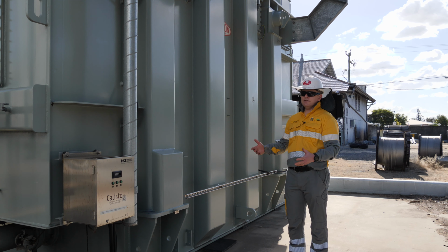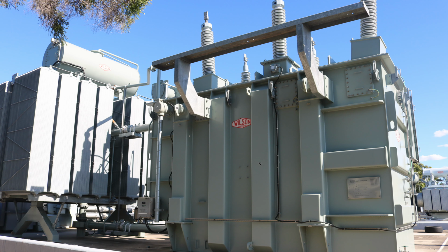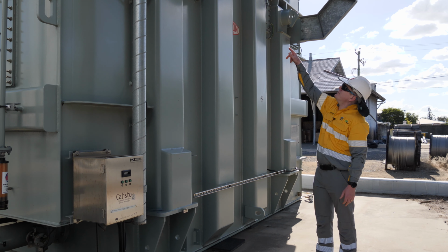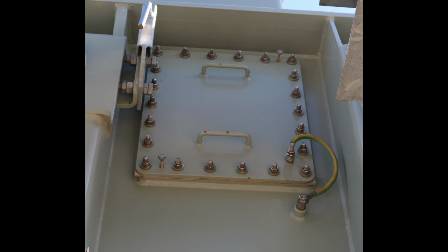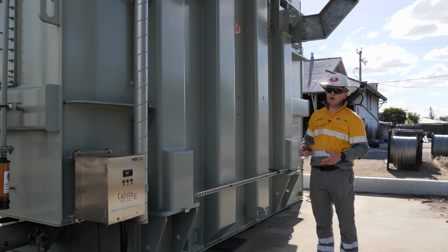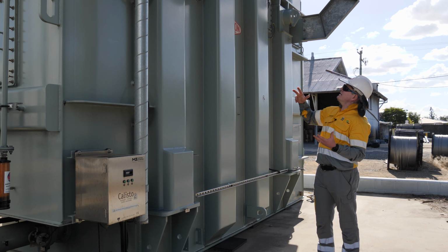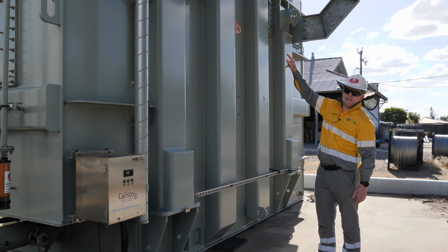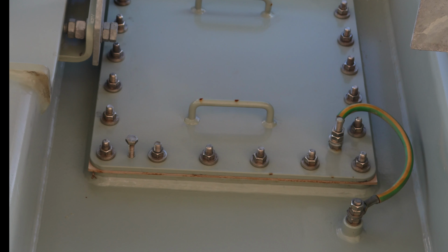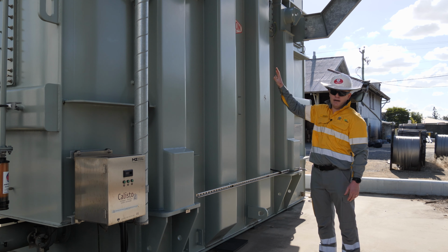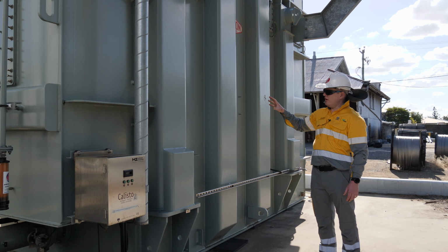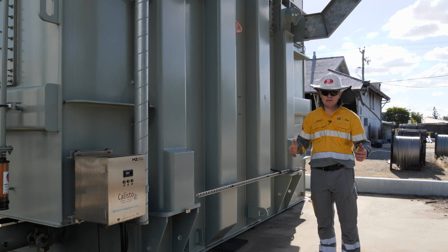Alright, so we've moved around to the other side of the transformer now, and there's a few more features that we can point out here. At the bottom of each of these HV bushings is an inspection hatch plate, which is basically a metal plate that can be removed once the oil has been dropped, so that bushings can be disconnected and reconnected. One of the key features is that we have an earthing connection from the plate to the main tank to make sure that there's no potential difference between any of the parts on the transformer, and that the whole unit is kept at the same potential.